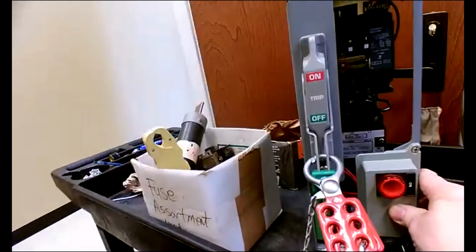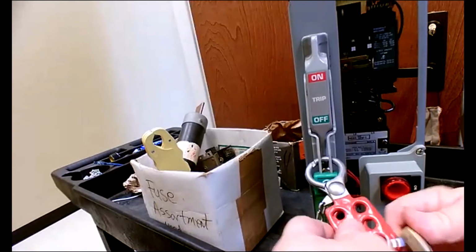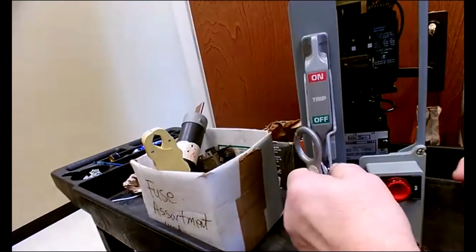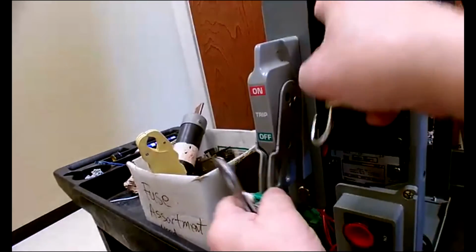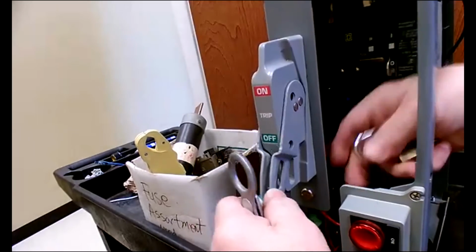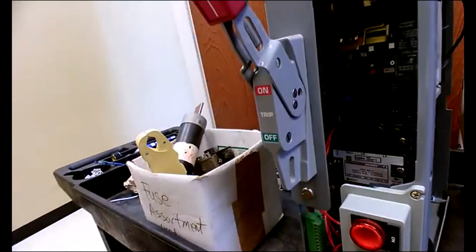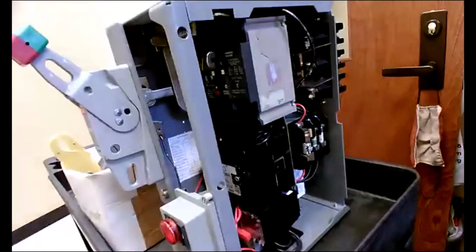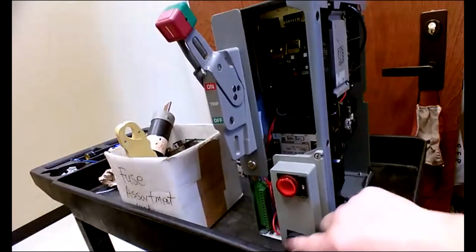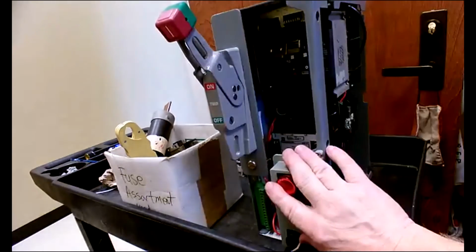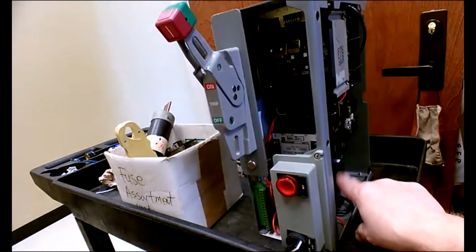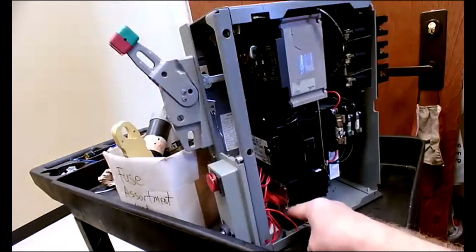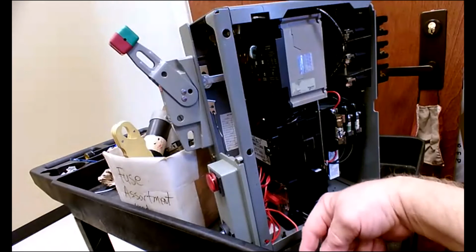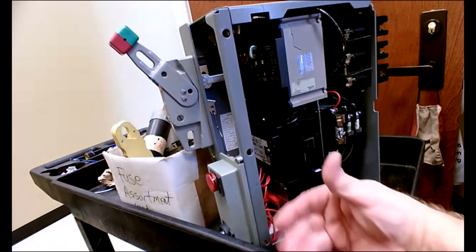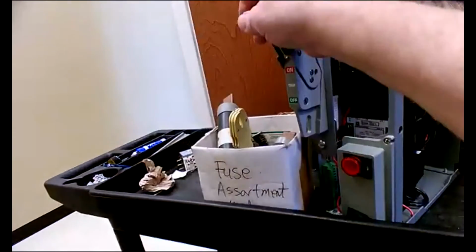Now here we've got a motor control center right here. Let me back it up. So y'all see here that we have a unit that's got a circuit breaker in it. It's got a motor starter. It's got some lights and all. This is a main disconnect. It would be for one motor control center. So let's say that I've got to work on the motor itself, the motor that gets connected to this, where the wires go out of the motor starter and go to a motor. I'm going to work on the motor, okay? So I come over here and I cut that off.